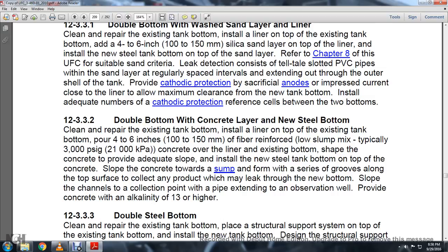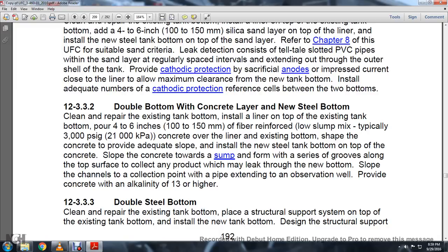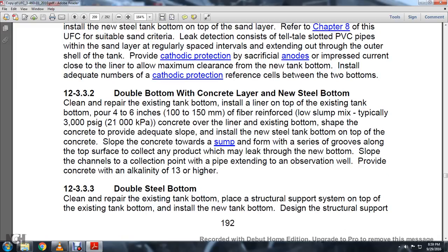Section 12-3-3-2: Double bottom with concrete layer and new steel bottom. Clean and repair the existing tank bottom and install a liner over the top. Apply four to six inches of fiber-reinforced concrete, typically 3,000 PSI, over the liner. Shape the concrete to provide adequate slope. Install the new steel tank bottom on top of the concrete. Slope the concrete toward a sump, with grooves along the top surface to collect any product leaking from the new bottom, channeled to a collection pipe extending to an observation well. The concrete should have an alkaline pH of 13 or higher.